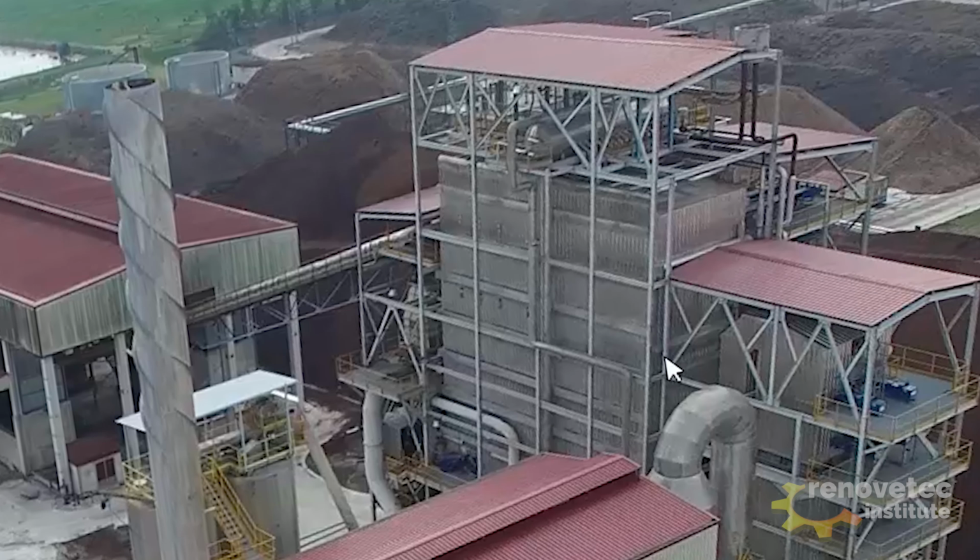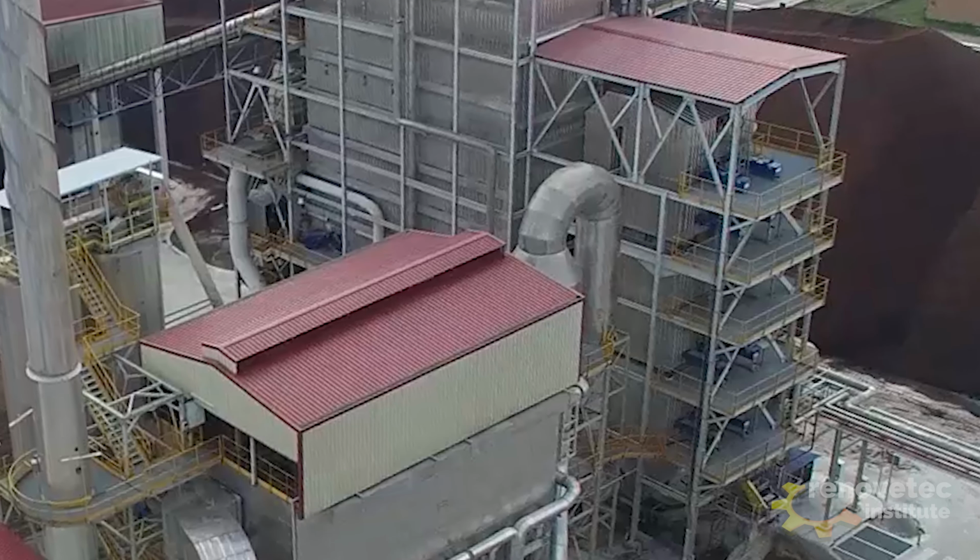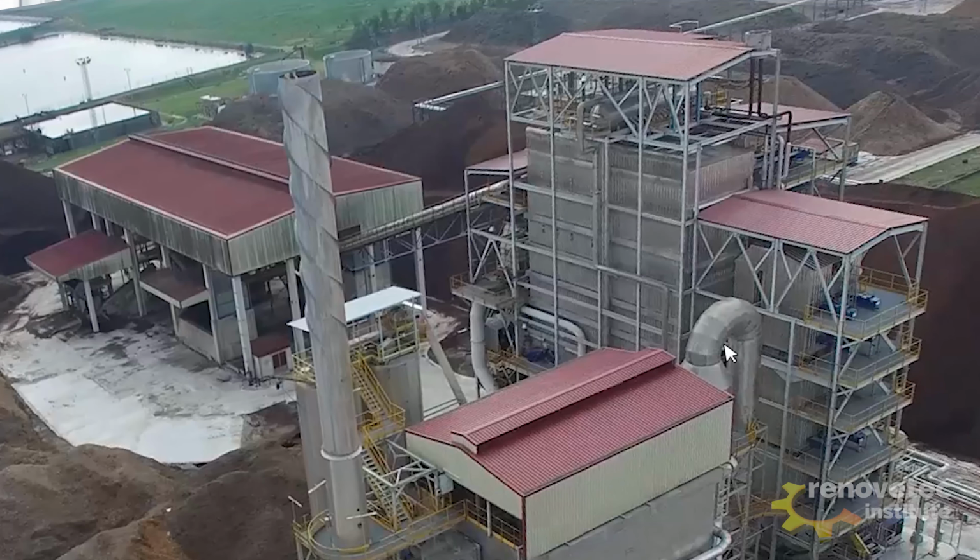In this case, the steam turbine is located out of this area. There, then, we have the grill, the water wall, the evaporator section, the drum, and the superheater. But here, in this area, we recover the energy contained in the flue gas, and there first we preheat the water till the evaporation temperature, and after we preheat the combustion air. Then this is the recovery section, this is the furnace.